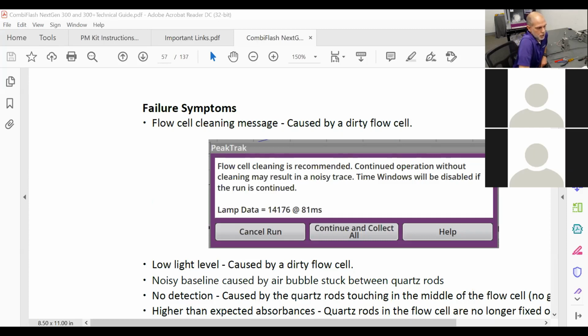Now, when this message comes up, you want to do a flush. That's the first thing you want to do with the flow cell, okay? Flush it. Like I said, I like to use methanol or acetone. Please never, ever sonicate a flow cell. Do not put it in a sonication bath, all right? The reason for that is those quartz rods in there, they can shatter. We don't want that to happen to you, okay?